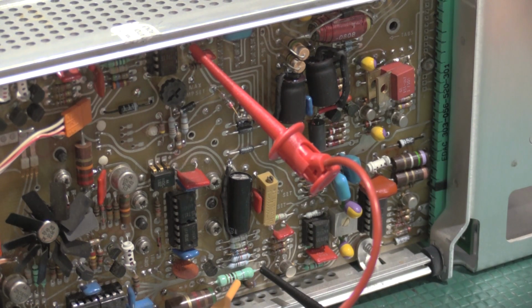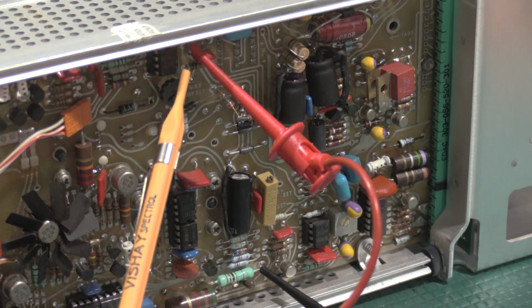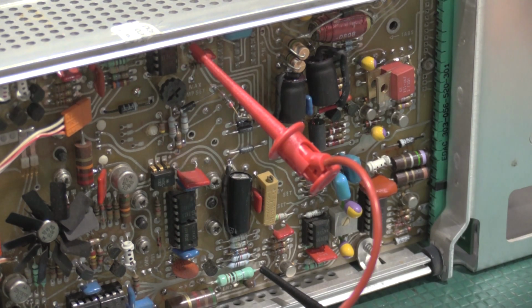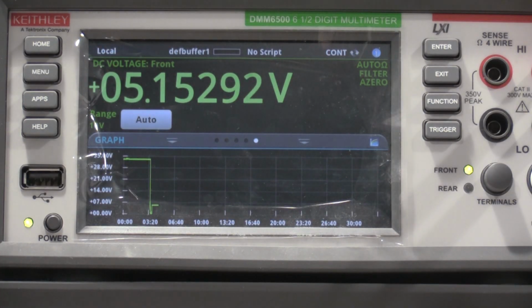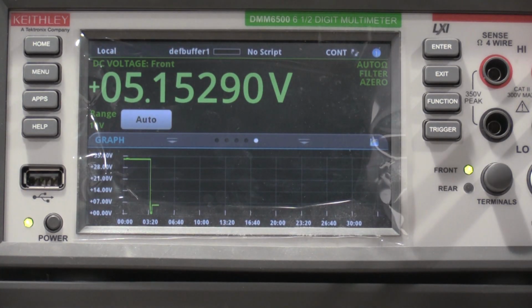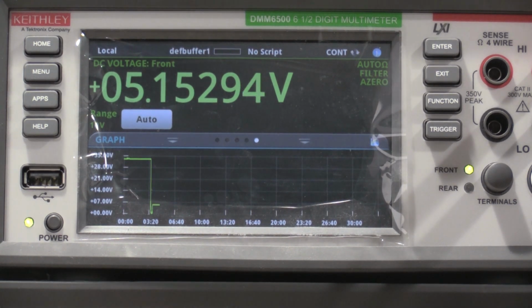Okay, I'm set up to test the 5.2 volt supply. Ground is picked up from this resistor down at the bottom. 5.2 volts is up here at the top. And I'm reading 5.15. I will move you guys over to the meter. 5.15. And I'm allowed 4.9 to 5.5. So that is fine.